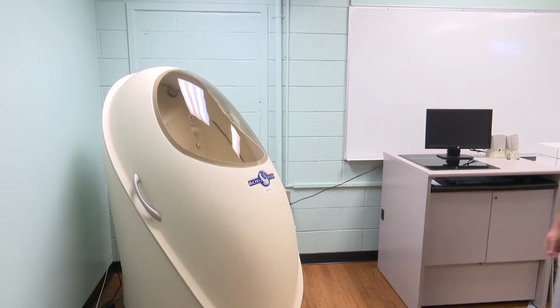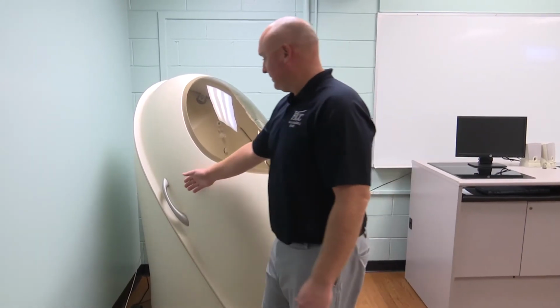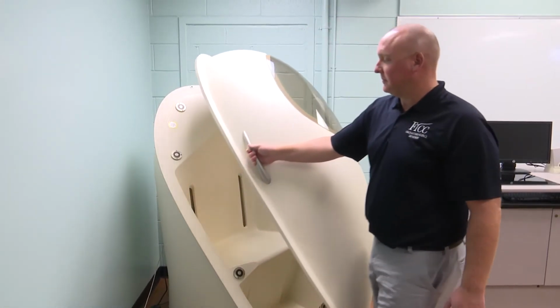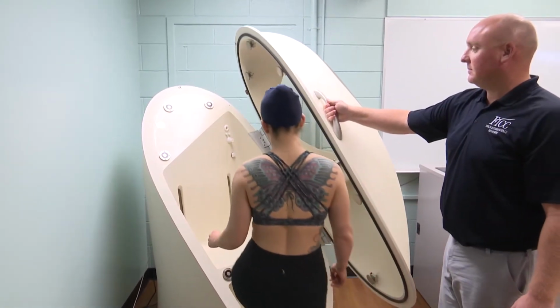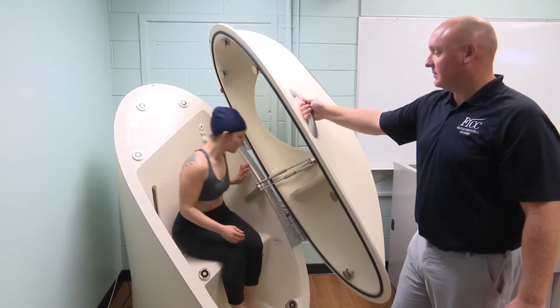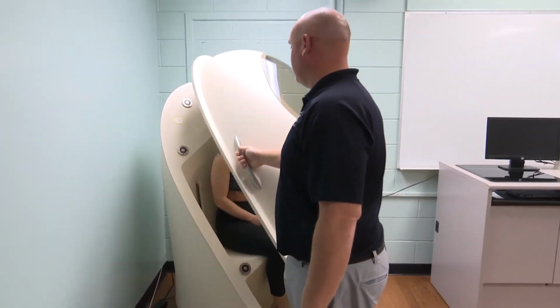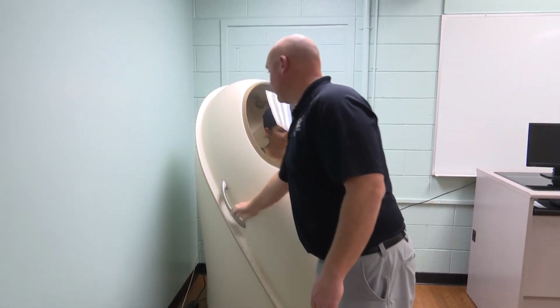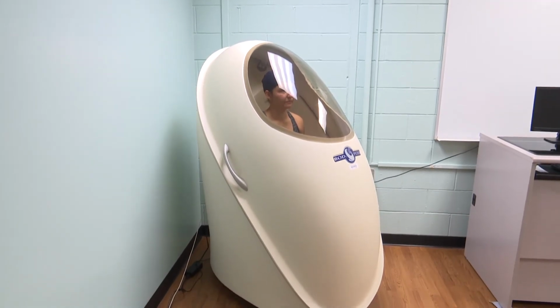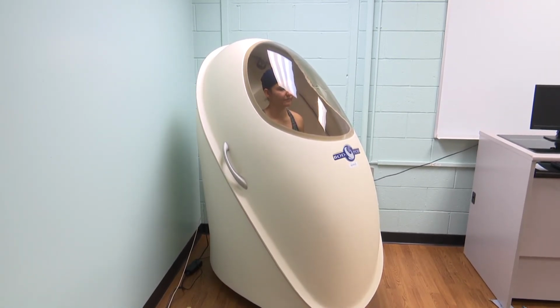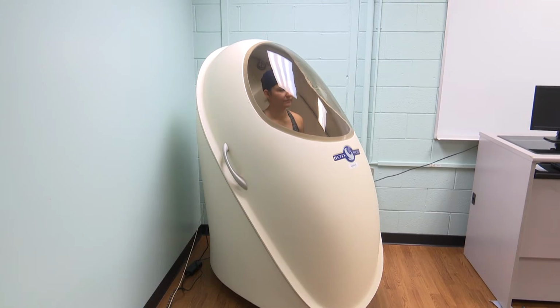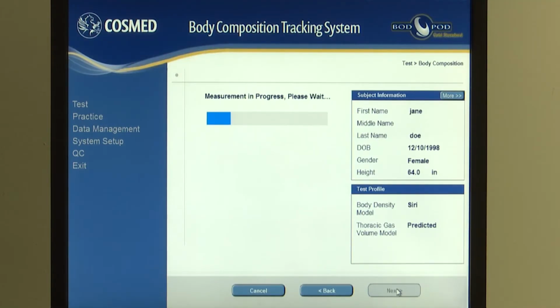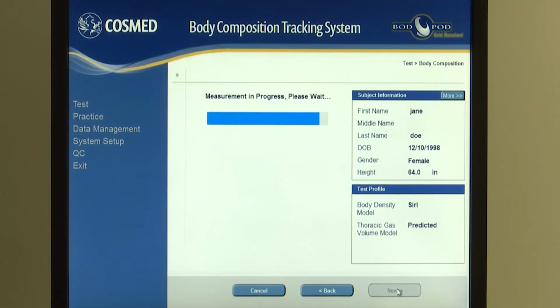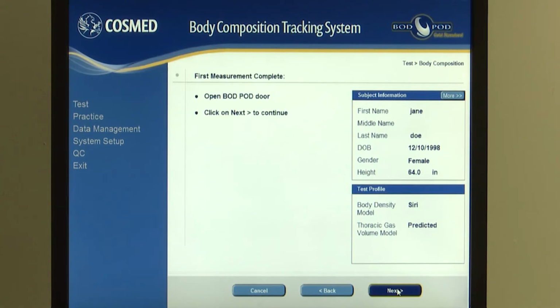Inform the client to sit all the way back in the Bod Pod and remain as still as possible and to not hold their breath while in the Bod Pod. The door will be opened between each measurement. This is also a good time to make sure your client is doing okay and not feeling claustrophobic or panicky. The Bod Pod will conduct 2 to 3 measurements, each measurement lasting approximately 45 seconds.